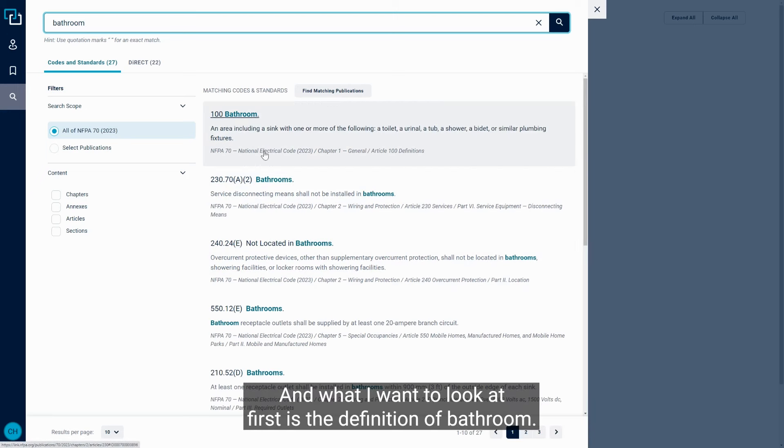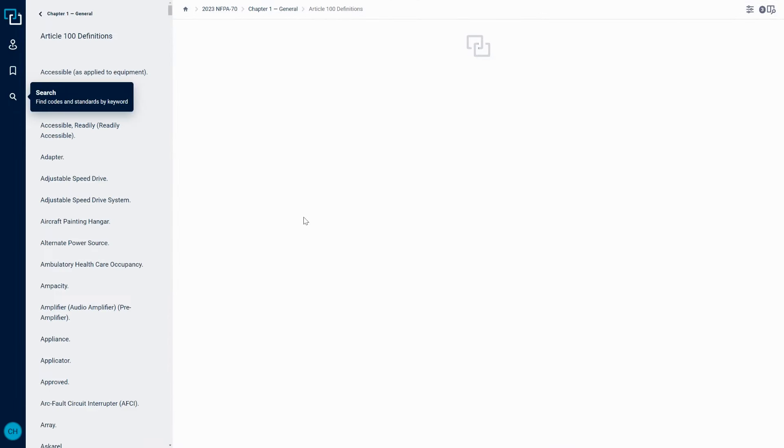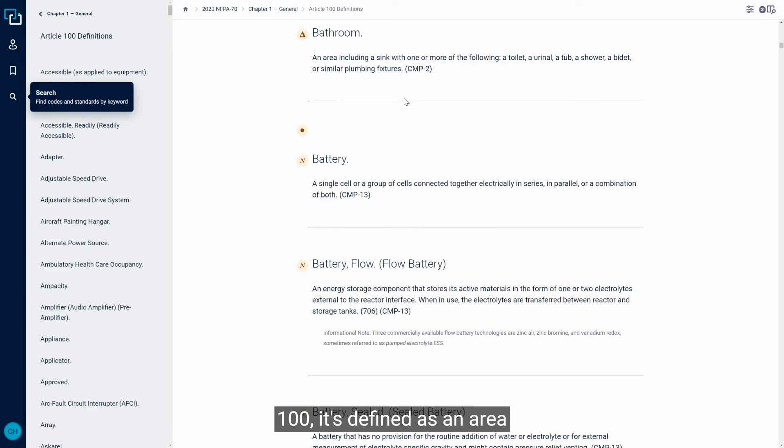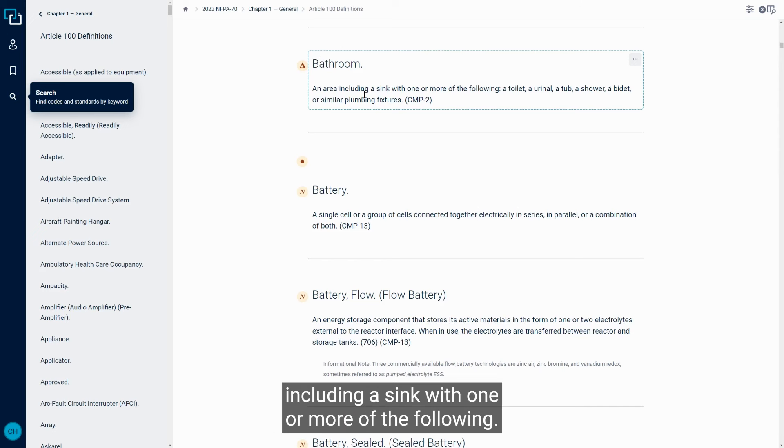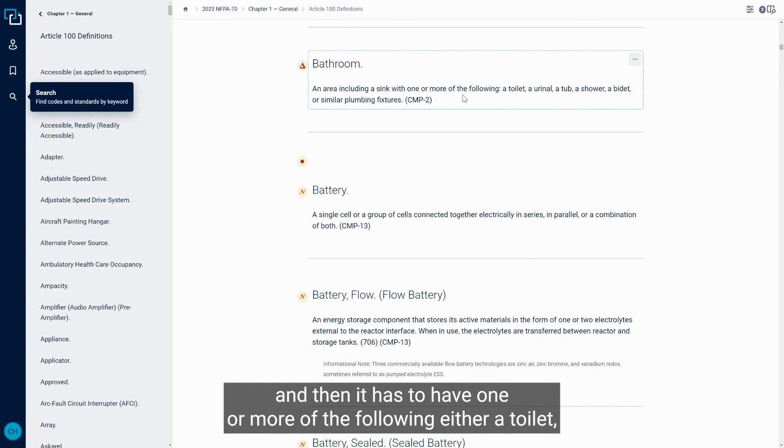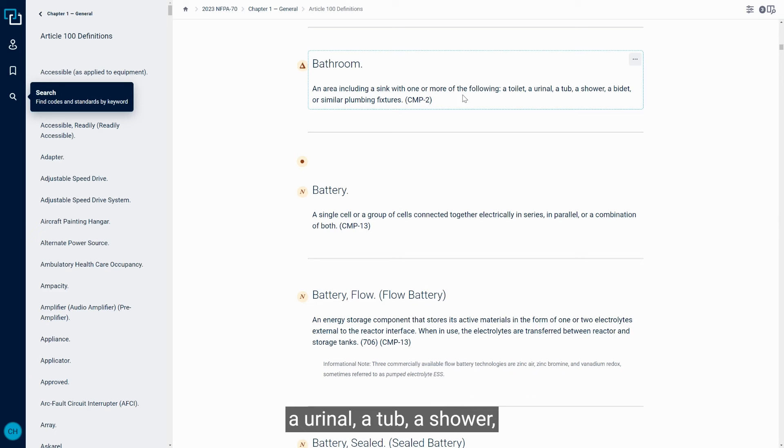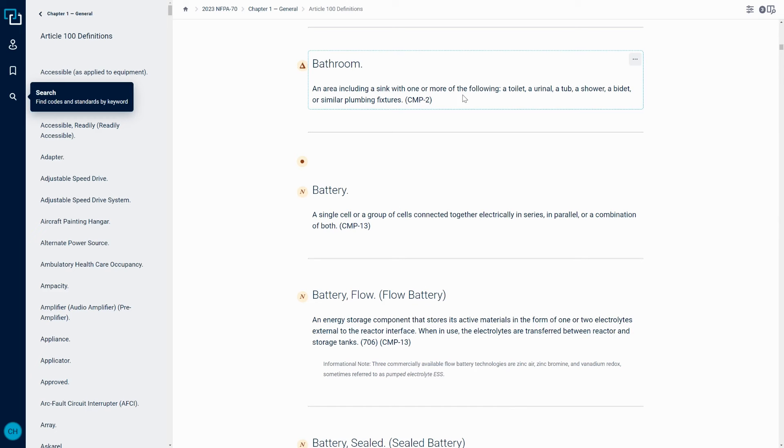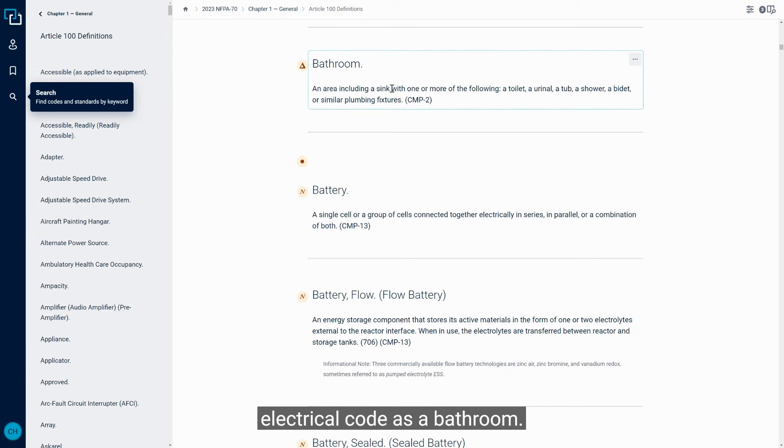And what I want to look at first is the definition of bathroom. So if we go to the definition of bathroom in Article 100, it's defined as an area including a sink with one or more of the following. So the base level, it needs to have a sink in it, and then it has to have one or more of the following: either a toilet, a urinal, a tub, a shower, a bidet, or similar plumbing fixtures. So that's what's going to be defined based on the National Electrical Code as a bathroom.